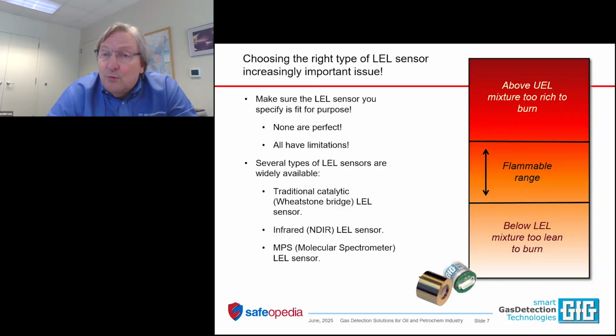Invariably, in a multi-gas instrument, one of the sensors is going to be an LEL sensor. There are several different varieties of LEL sensors available, and choosing the correct LEL sensor is really critical. Some of them are going to work, some of them may not work for your specific application. Each type of LEL sensor has specific advantages, but also disadvantages and limitations. So you really need to consider how you are going to measure the combustible gas. And I'll just briefly talk about the three major types of combustible gas sensors that are available for use in portable or fixed gas detection instruments.